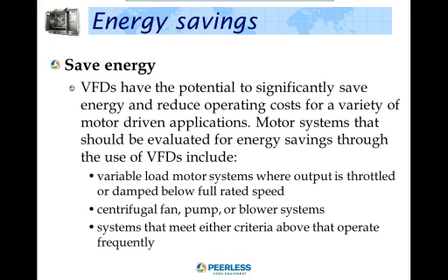Energy savings. Rising energy prices create a need for energy-efficient motor control solutions. To help reduce energy losses, process engineers are turning to VFDs as an alternative to fixed-speed controllers and throttling devices such as dampers and valves. Advancements in drive technology, careful selection of the hardware and power systems configurations, and intelligent motor control strategies produce improved operating performance and control capability and energy savings. Things to consider when choosing a motor control solution include peak demand charges, operating at optimized efficiency, power factor, isolation transformers, cost and losses, regeneration capabilities, synchronous transfer options, and specialized intelligent motor control energy savings features.